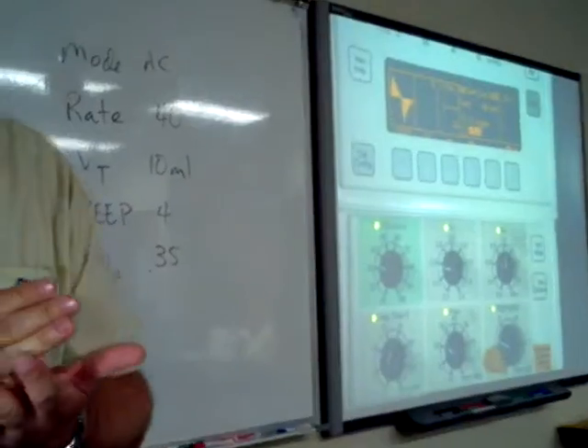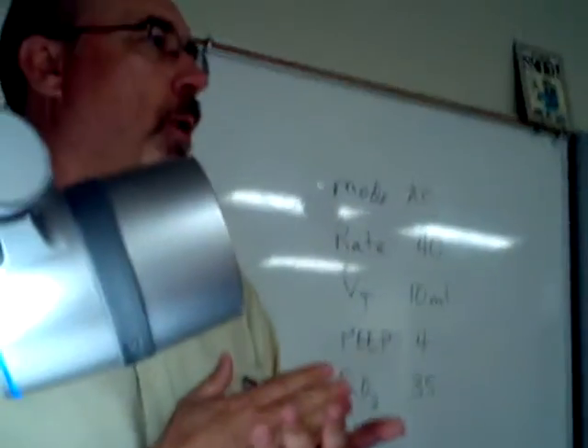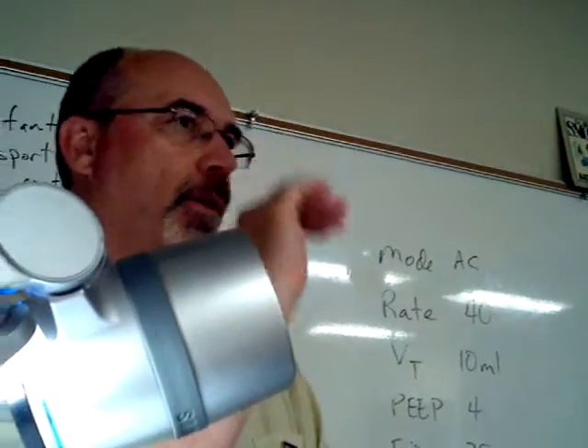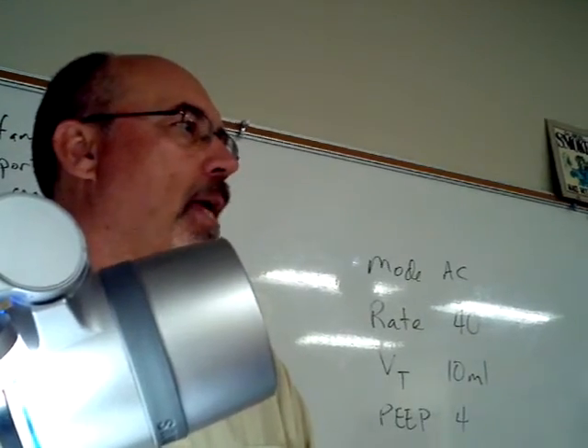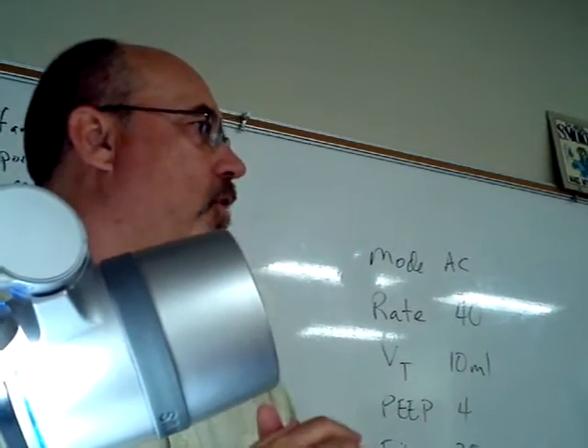That's how much flow the neonate has to generate so the machine knows they want a breath. So you want to make sure you set that. That's one of those things you'll just have to remember. So put an underline under set trigger level. You just have to remember that in section 1. Once we set in that section, we're done. We'll just leave it there.